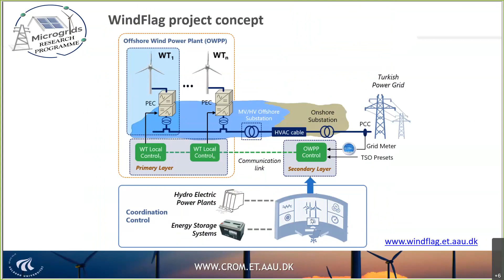Apart from WindFlag, which tries to work more on AC grids, we can see that something is happening as well with DC. When you have offshore wind farms that are far away, you start to think about using DC. And if you have DC with a number of connections, what we call multi-terminal HVDC networks, then the main control used is also droop control, because basically you want to share power between one station and the other. This way you can decide how much power comes from one station to the other, so you have full control.